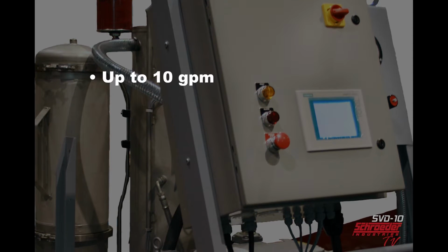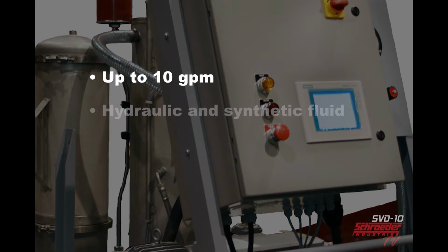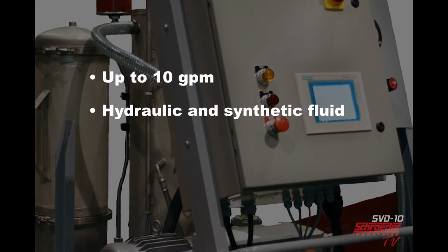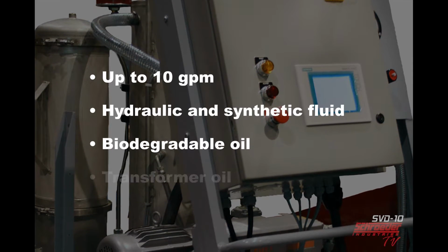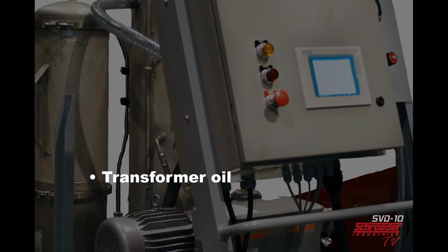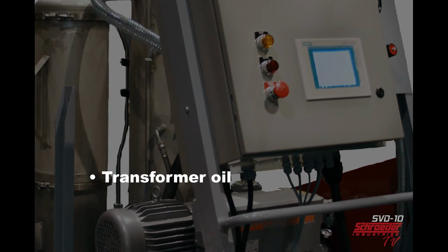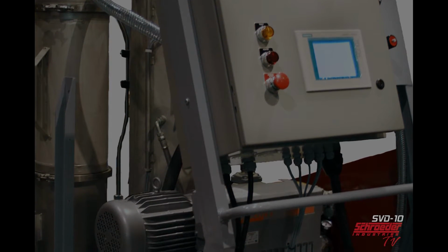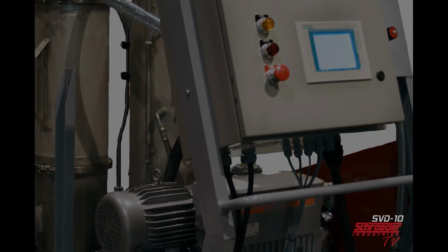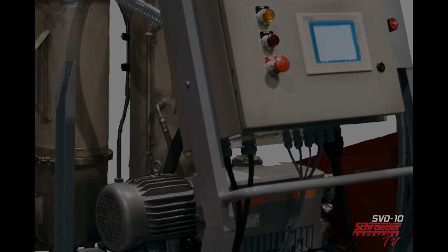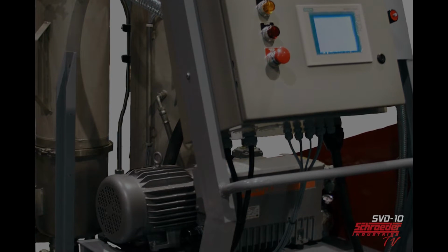The flow rate for the SVD10 is 10 gallons a minute and it can extract free and dissolved water as well as free and dissolved gases and solid contaminants from hydraulic oil and synthetic oils, biodegradable oils, and also transformer oils. But for the transformer oil option to work, you must opt to include the heater. It can also work with fire-resistant oils, but you must identify the fluid type, as this will help us determine if the SVD10 is the best option for you.